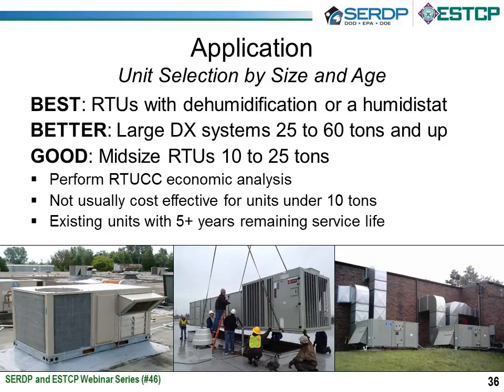Really, the way to tell whether these gray area RTUs are economically justified is to perform an RTU-CC. It's a rooftop unit comparison calculator, an online software tool from Pacific Northwest National Lab, for economic analysis, and we can do that. Typically, we find that it's not cost effective for units that are smaller than 10 tons unless there is a strong dehumidification need. And for existing units, you want to have at least 5 years of remaining service life. The unit needs to be in good condition and still with the original compressors, not had a compressor replacement.